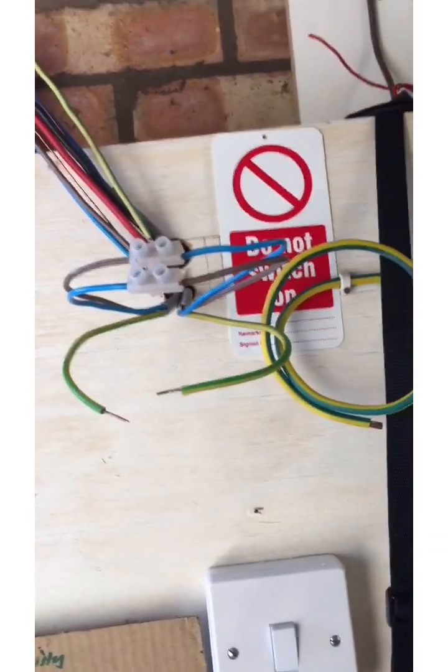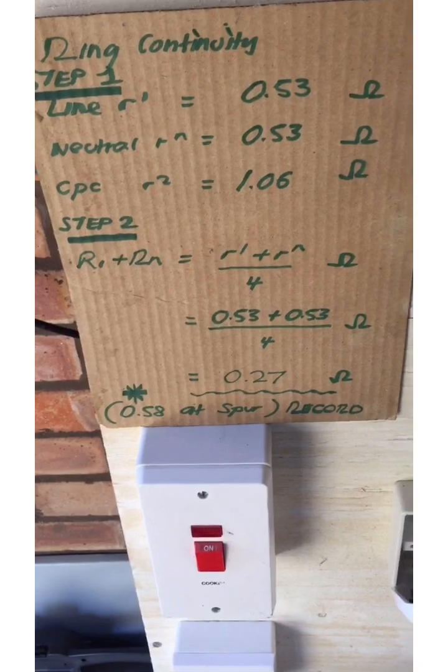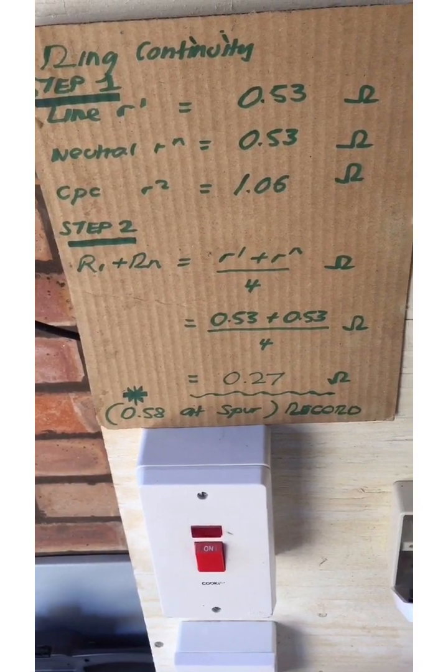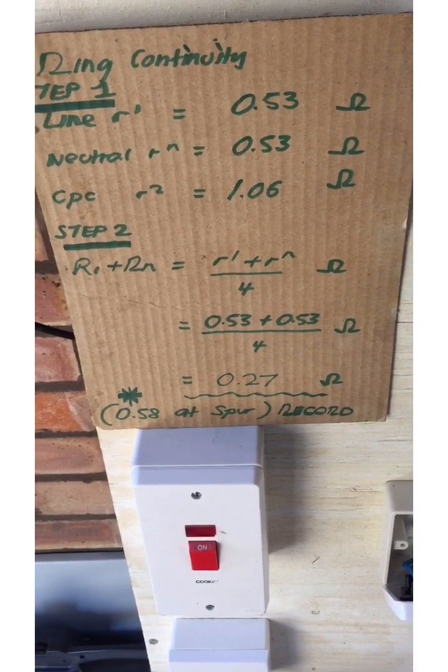So what we can do now is, the expected value that we are looking for here, if you look at step two, because of the way that we've connected them, we expect the R1 plus Rn value, which is what we take at the socket outlet, to roughly equate to the maths that we've got there.